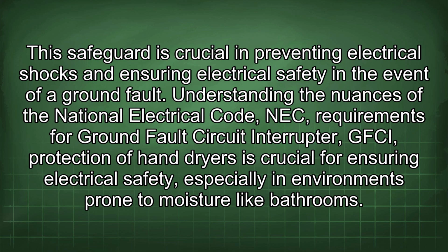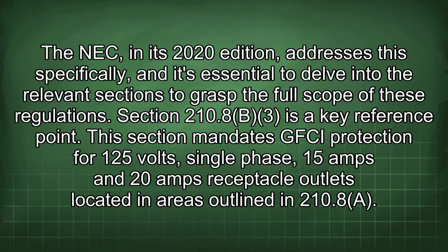Understanding the nuances of the National Electrical Code (NEC) requirements for ground fault circuit interrupter (GFCI) protection of hand dryers is crucial for ensuring electrical safety, especially in environments prone to moisture like bathrooms. The NEC, in its 2020 edition, addresses this specifically, and it's essential to delve into the relevant sections to grasp the full scope of these regulations. Section 210.8(B)(3) is a key reference point.